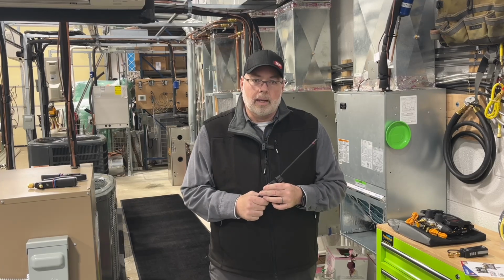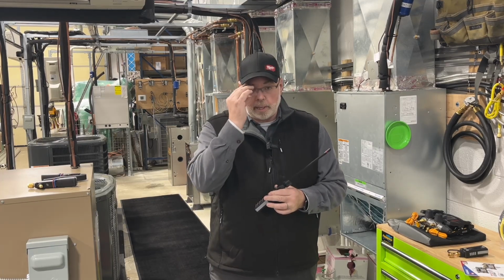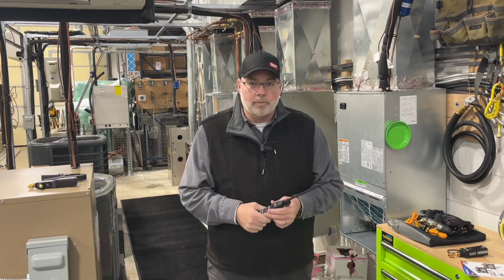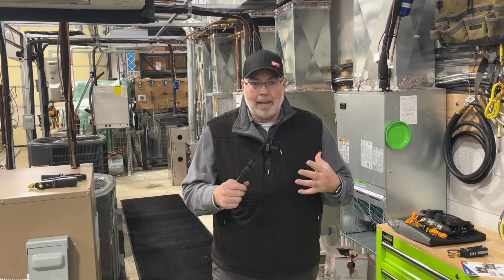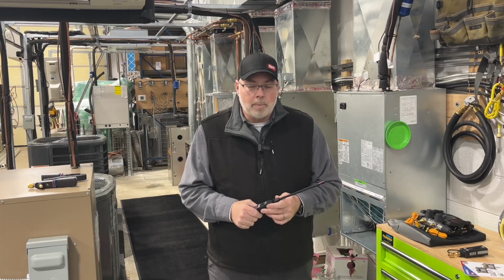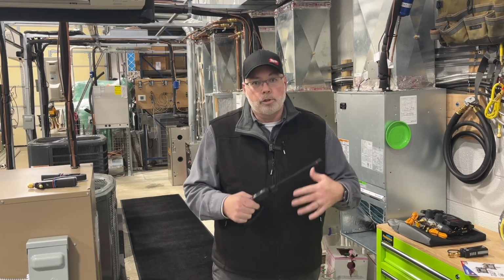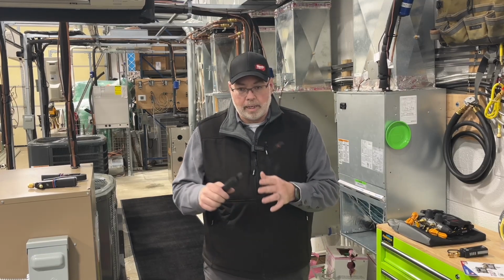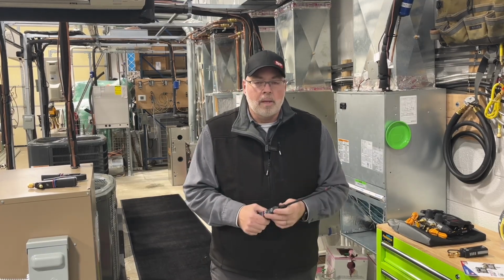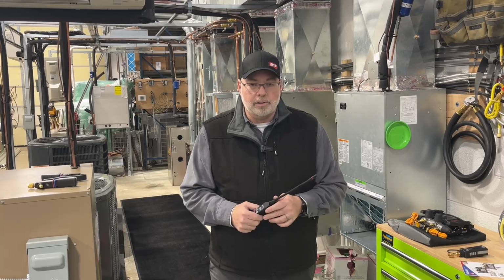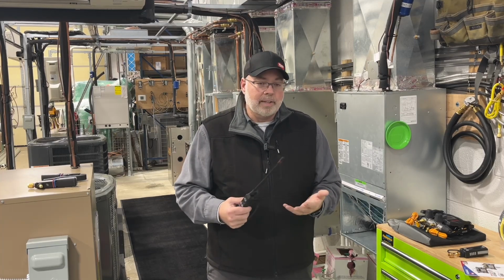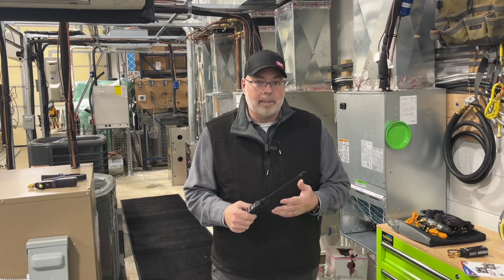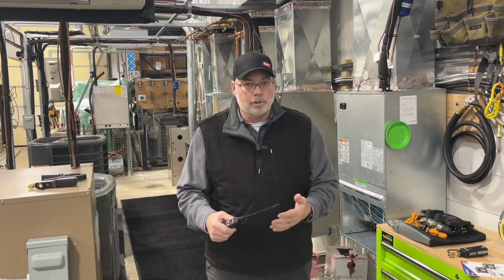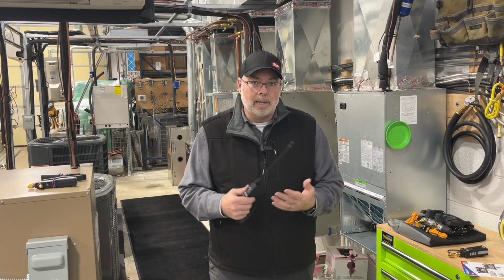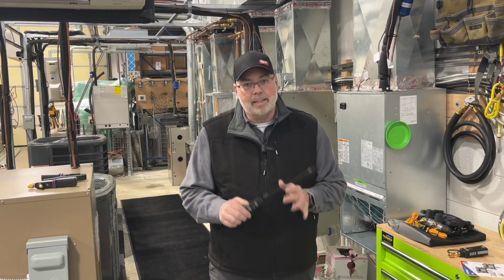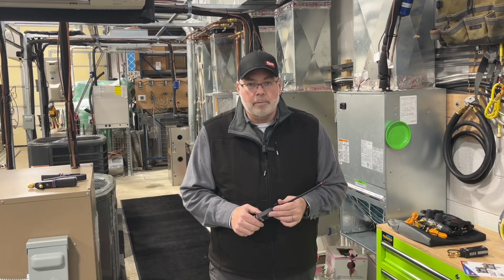Having done tech support for many years, we would get calls from technicians and ask for information such as return and supply temperatures, but we would also ask for return and supply wet bulb temperatures. So we needed not only dry bulb, but also wet bulb so we could see what's really happening across the evaporator coil. Often we found that technicians did not have the ability to actually measure a wet bulb in the airstream, which made it very difficult when trying to really dial in and find out exactly what's going on in the refrigerant system.